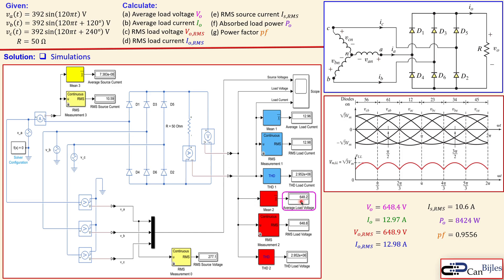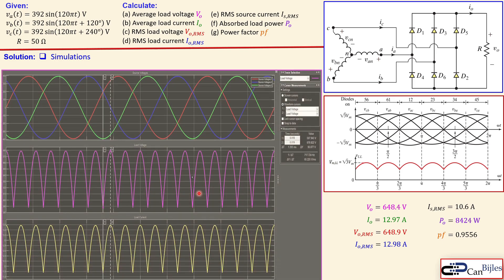Going through the results one by one: the mean average load voltage from simulation is 648.2 volts versus our calculated 648.4 — very close. The average load current is 12.96 versus calculated 12.97. The RMS load voltage is 648.8, also close to the calculated value. The RMS load current is 12.98 amps, exactly matching our calculation. The source current RMS is 10.58 amps versus our calculated 10.6 — all values check out.